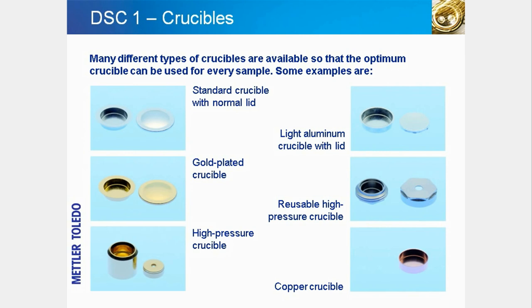Mettler-Toledo offers different types of crucibles to suit different sorts of samples. The standard DSC crucible is light and sturdy and easy to handle. It is made of pure aluminum to ensure good thermal conductivity. The crucibles can be hermetically sealed, left fully open, or covered by a pierced lid. The diameter of the hole in the lid determines the degree of gas exchange with the surroundings and can therefore influence evaporation or reaction processes.